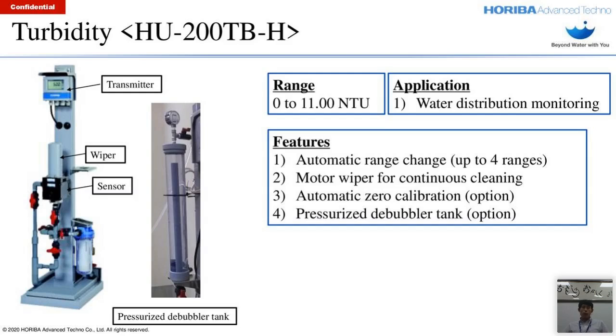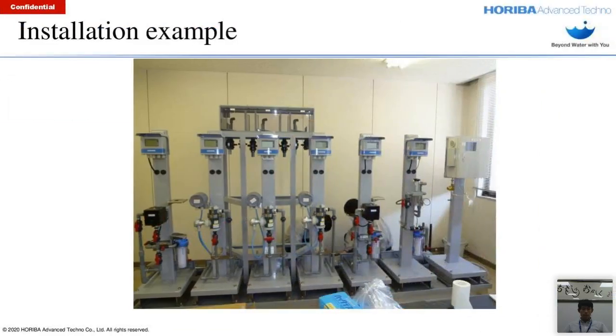For points three and four, we have automatic zero calibration and a pressurized debubbler as options to help the user better manage his or her process. This is very important because the sensor uses a laser to measure the turbidity. So when there are air bubbles present in the water, the readings will be affected. In this case, we highly recommend you to get the debubbler as well to remove the air bubbles for more stable measurements.